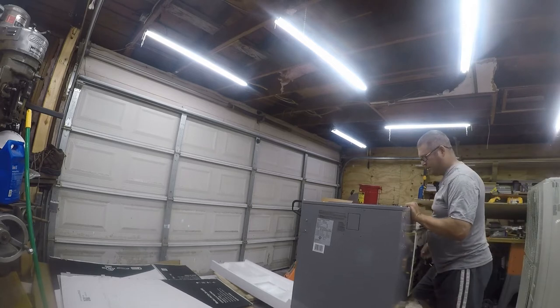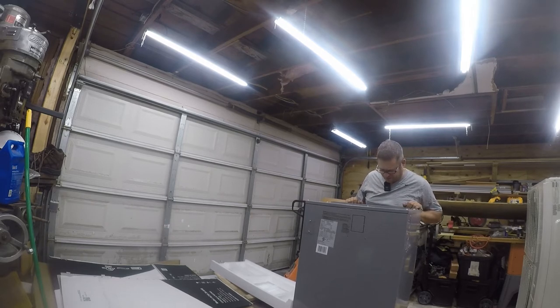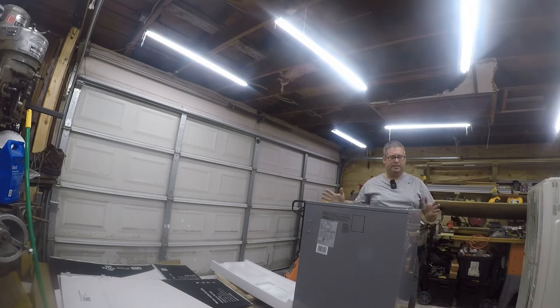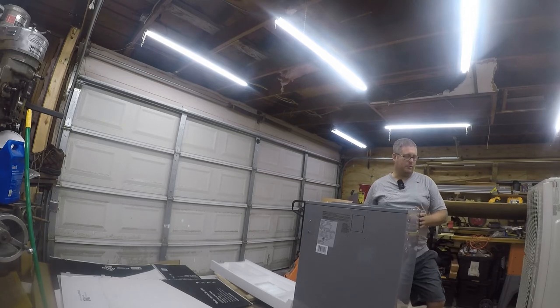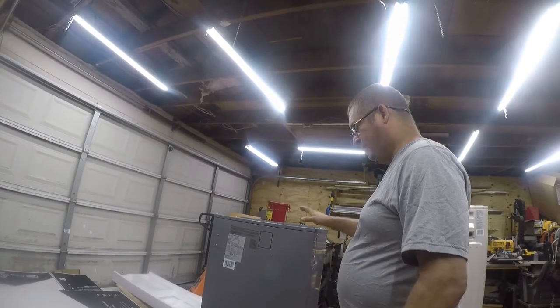It's got a good squirrel cage fan and there's a mount for the 5kW heat strip. It is wired a little bit weird compared to an American unit — the 5kW heat strip has its own wiring, and the fan and internals are controlled by the outside unit. It may require a double disconnect. Code says you're supposed to be able to turn off the power to work on it, and I'm not sure if having two separate circuits on one piece of equipment meets code. But it'll work for me — I've never used my 5kW heat strip to begin with.